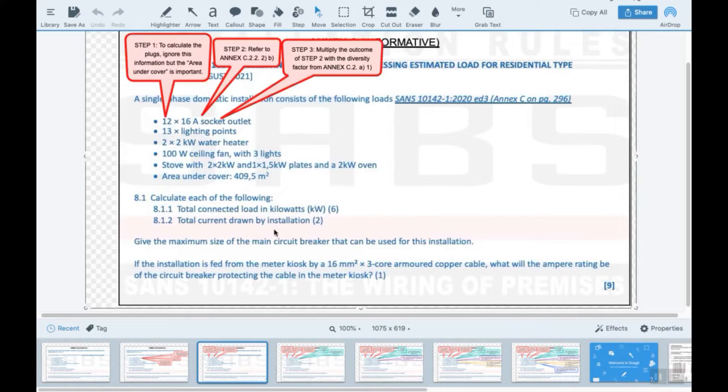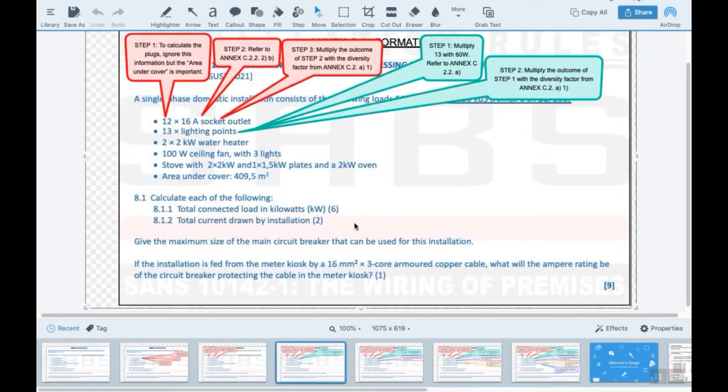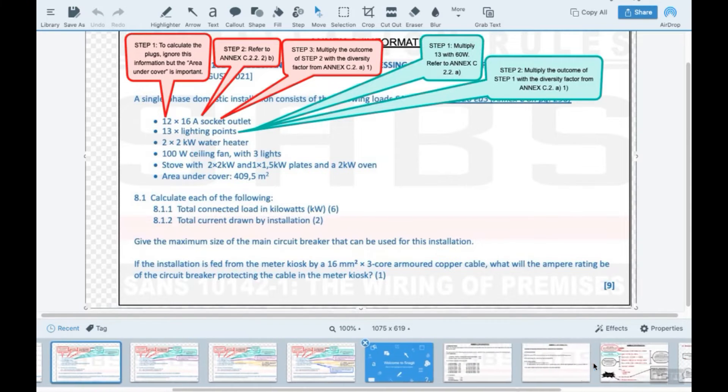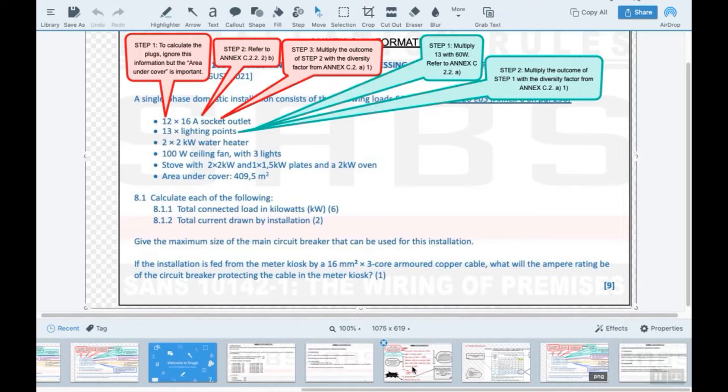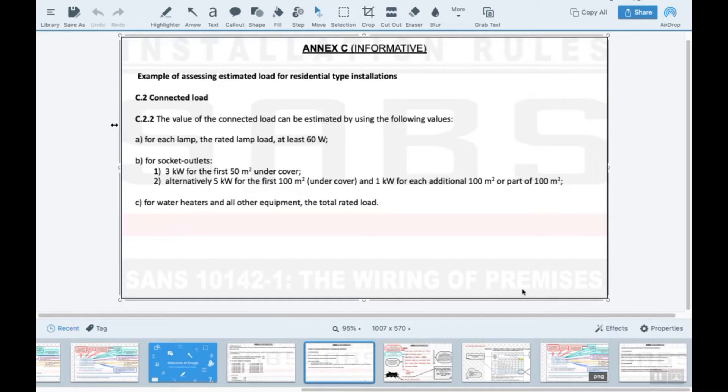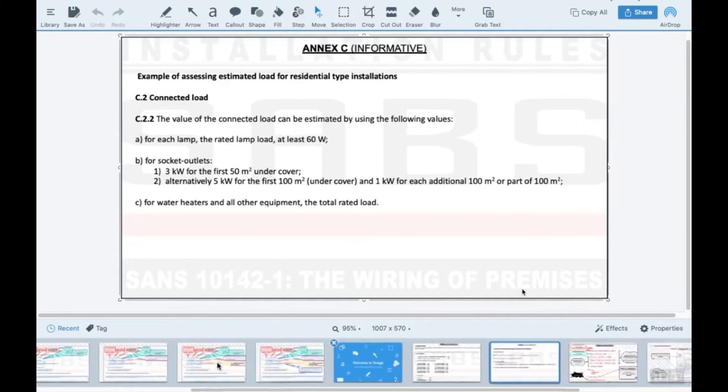So I've summarized that slide. Then the lights we would look at again, SANS Annex C. Where do I get this? I get this here: C 2.2A for each lamp at a rated lamp load at least 60W. So if you have one lamp it would be one lamp times 60 watt. If you have 13 lamps, it's 13 lamps times 60 watt. That's what this means.